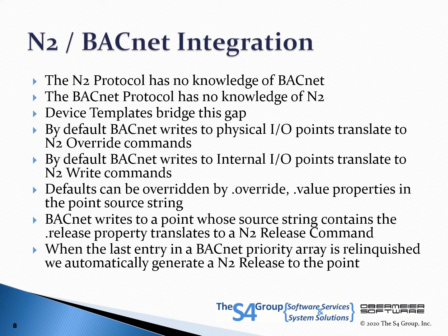S4 device templates are the key to defining how BACnet transactions are mapped to N2 transactions. The mapping is not always one-to-one. We may need to issue multiple N2 transactions to execute one BACnet transaction. BACnet has no knowledge of the specifics of N2 transactions or operational properties.